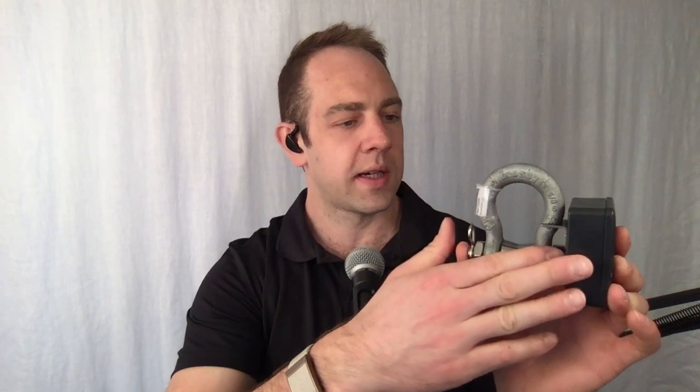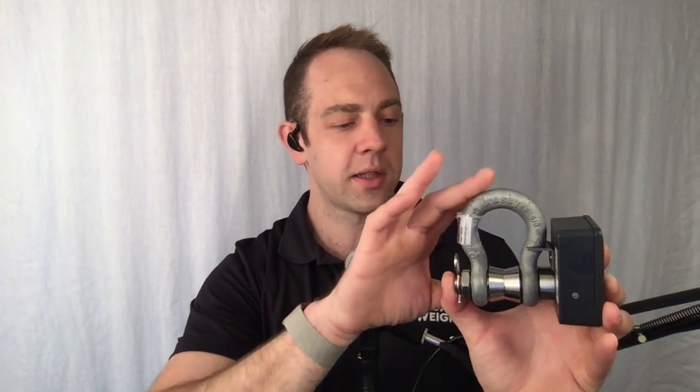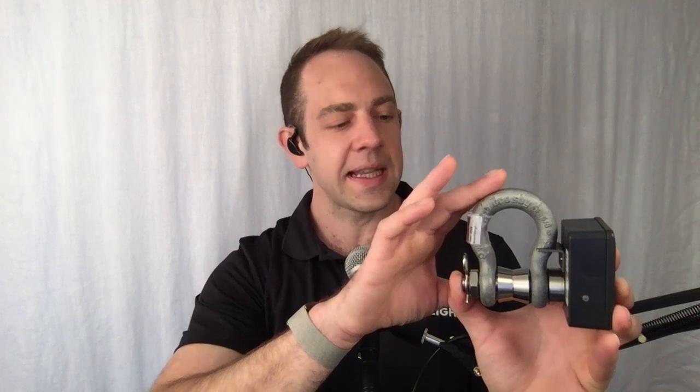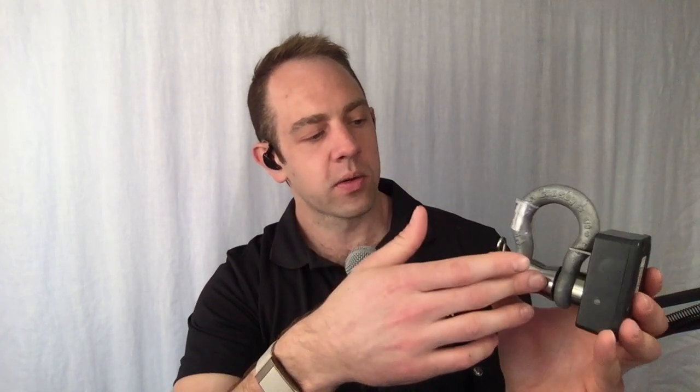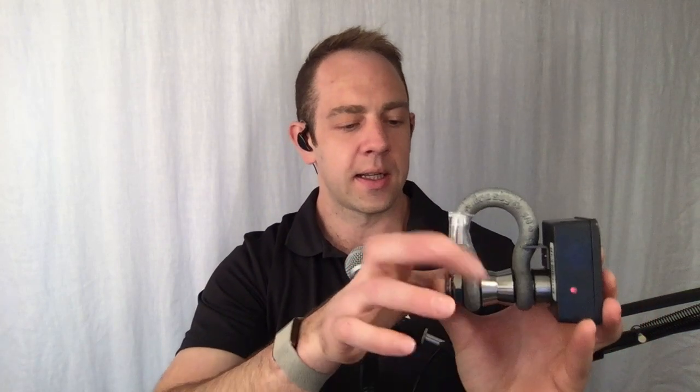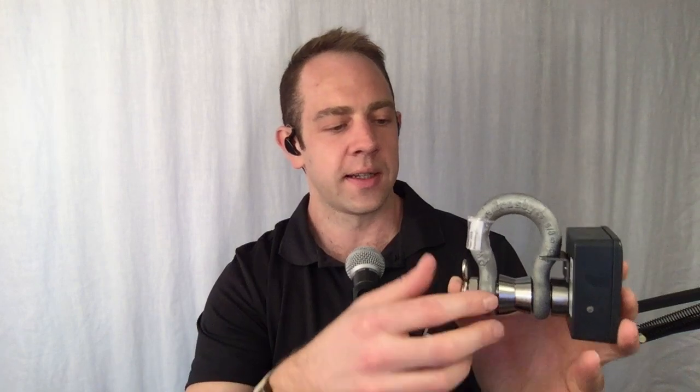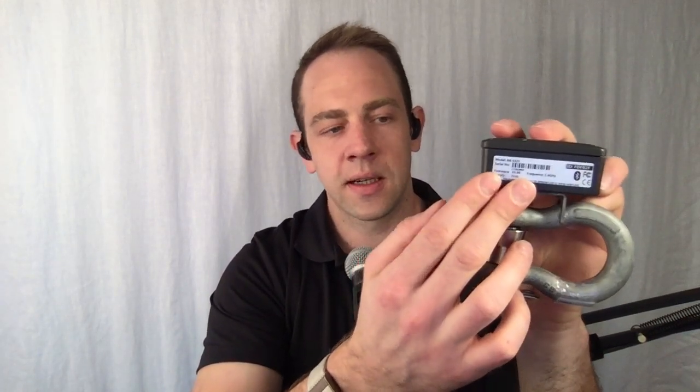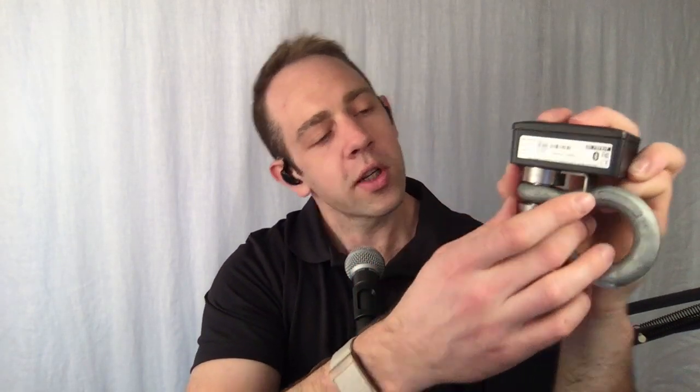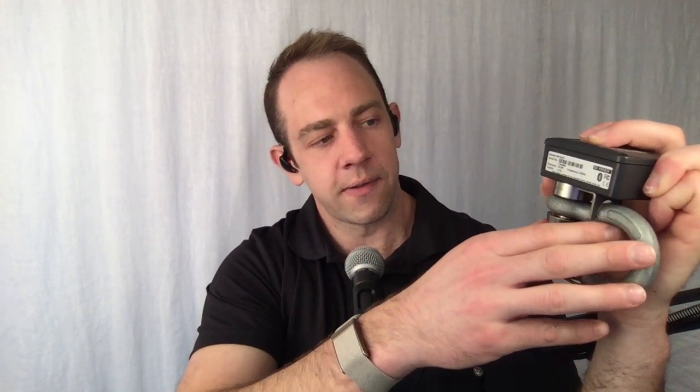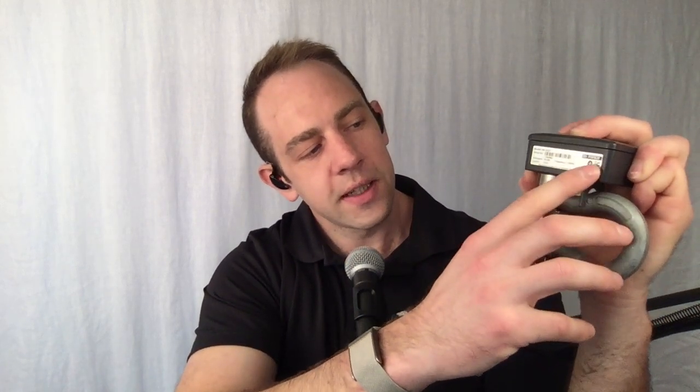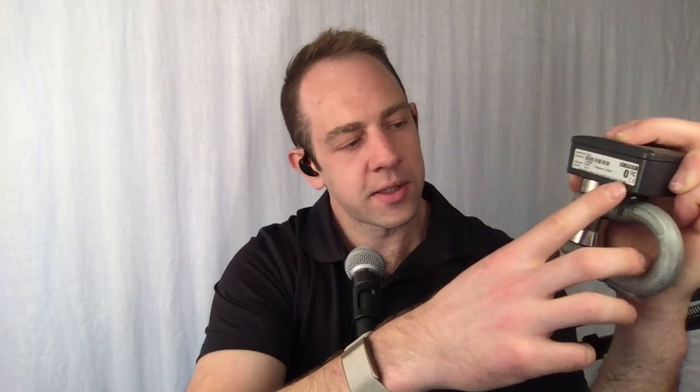We have the same typical shackle bow. So this is a 5/8 inch shackle, 3.25 ton capacity. Load centering bobbin here, so this centralizes our load right on the load pin to make sure our readings are accurate. Our enclosure box, as we mentioned. On the flip side, if we can see here, any of our info. If we're talking about our data tag, we're going to reference this later in the video. We're going to see our digits over here. So it says ID. We have six digits in there. So the data tag is going to be the last four digits within this ID range.